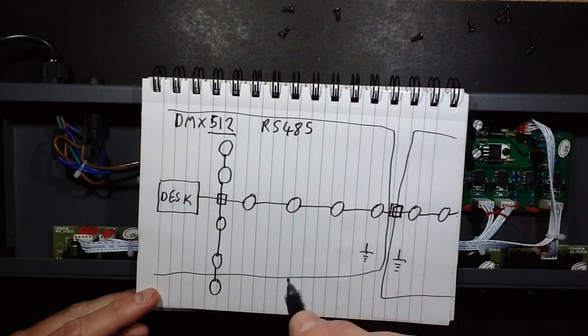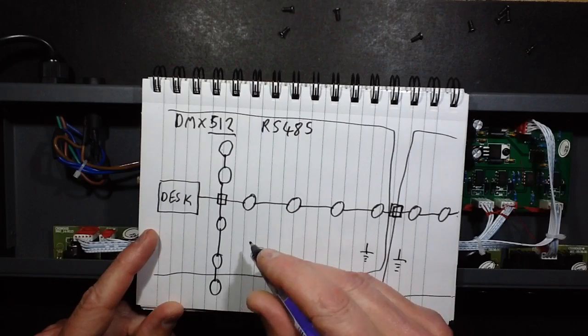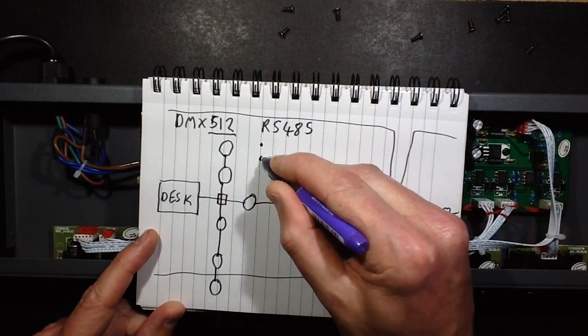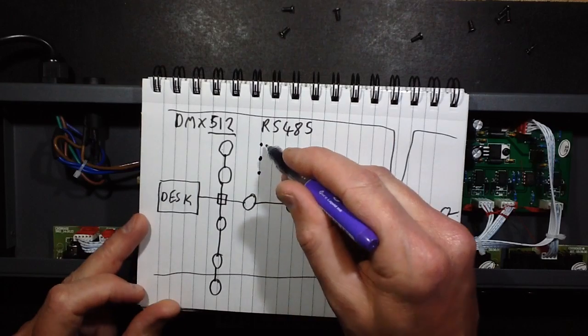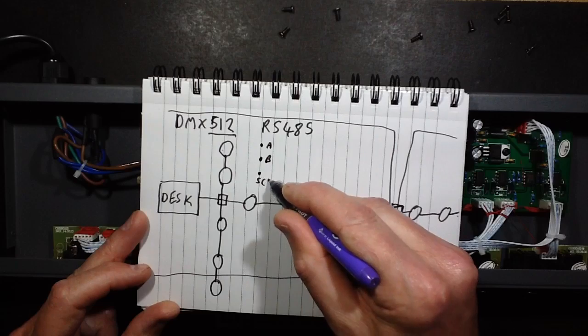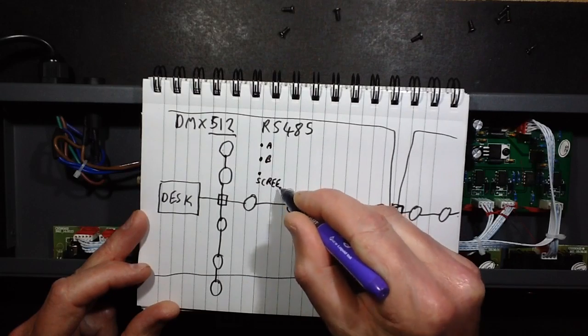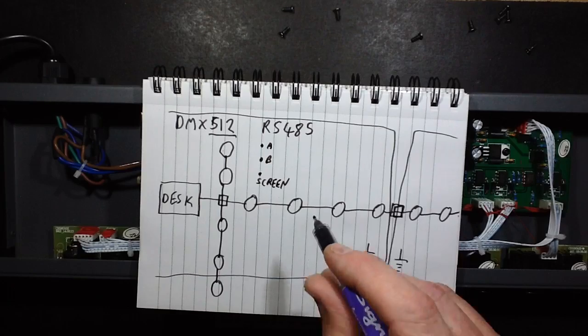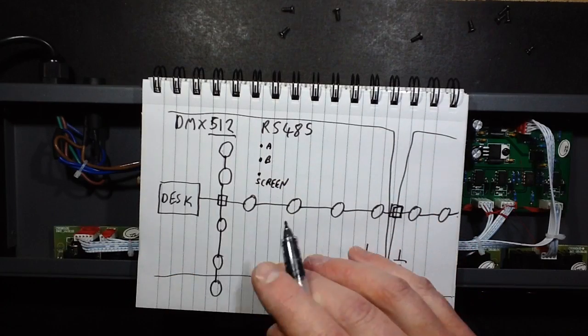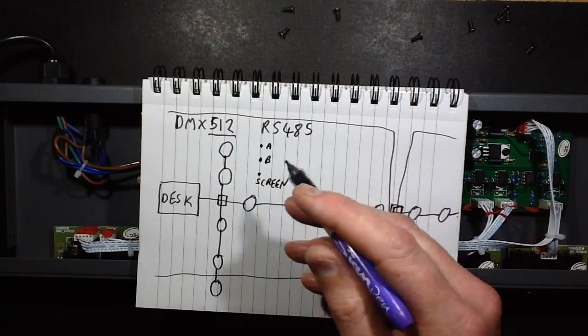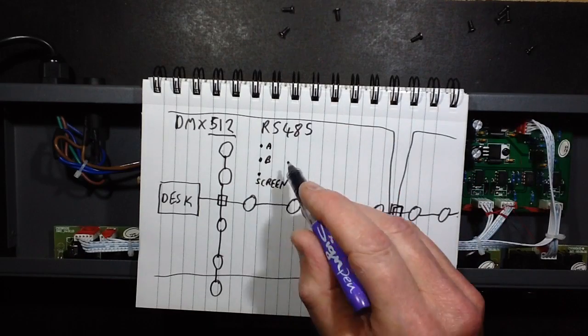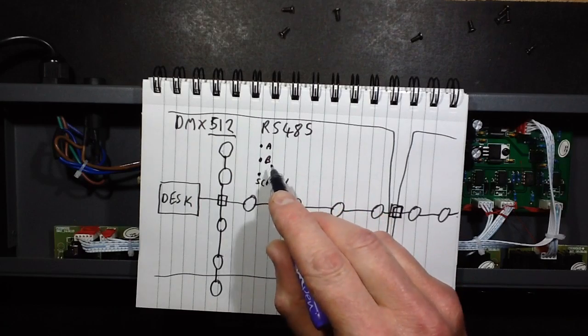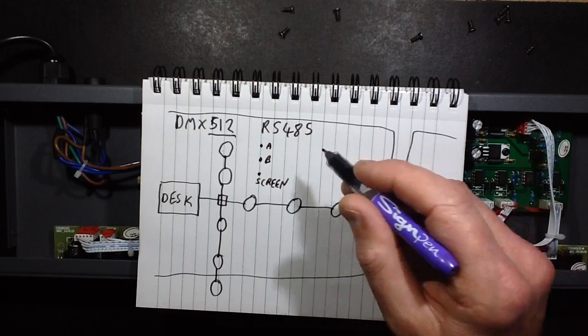On the subject of RS-485, it's quite interesting in that the RS-485 protocol has three wires in the electrical protocol which are basically called A, B and it's the screen cable which is also the common ground reference. To allow it to transmit data even though it's only about 5 volts, plus or minus 5 volts typically on something like this, will certainly push out plus or minus 5 volts, to transmit it the huge distances it can at very high speed.